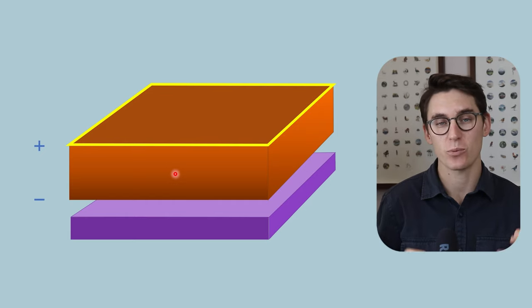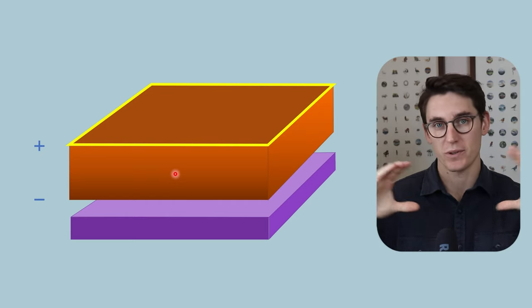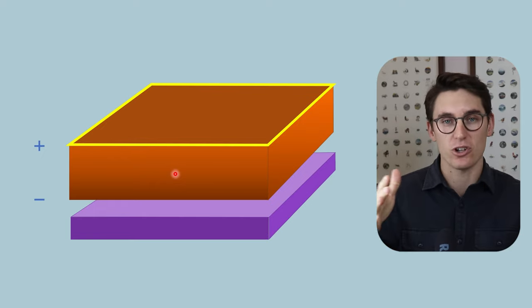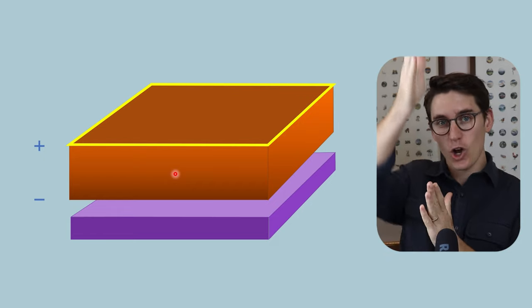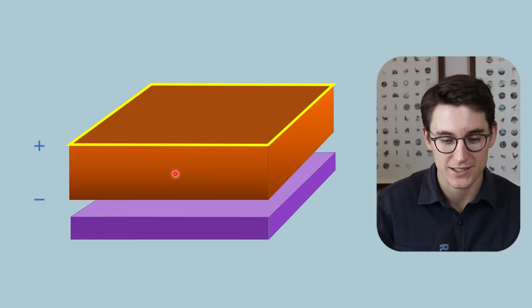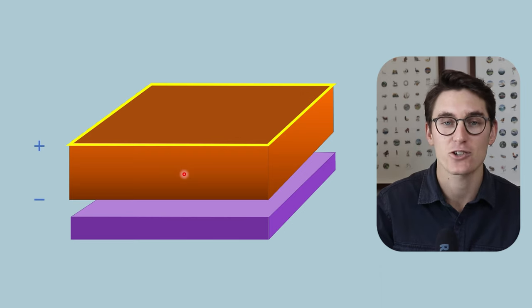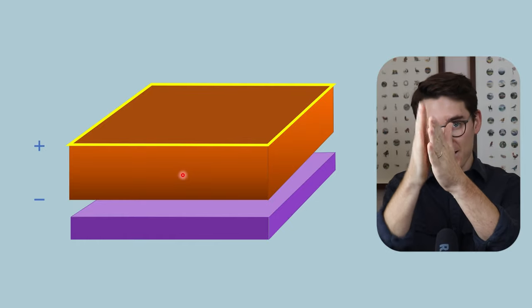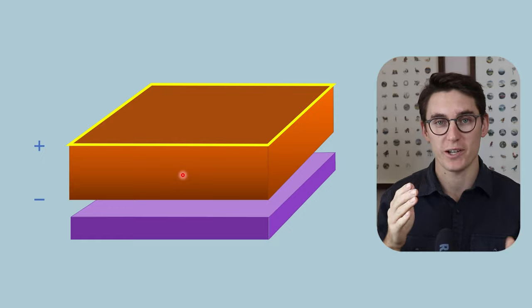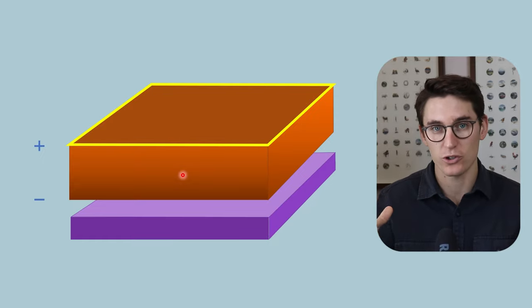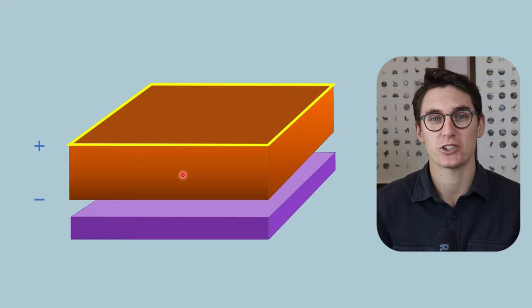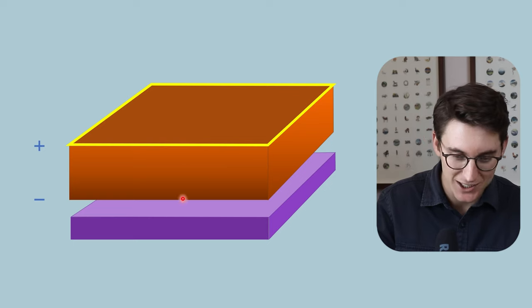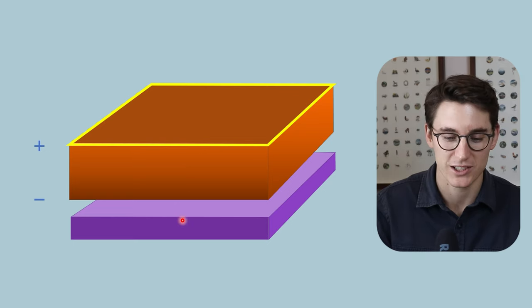Now the main difference here is that we haven't created light photons within a scintillation layer. When we create light photons, we get spreading out of that light photon. That hasn't happened here. Where our x-ray strikes this amorphous selenium is where the electron pair is created. Because of this charge differential, that electron will flow in the direct line of that x-ray. We've got very good specific spatial resolution here. We've got excellent spatial resolution.